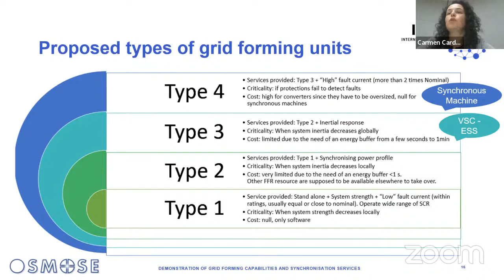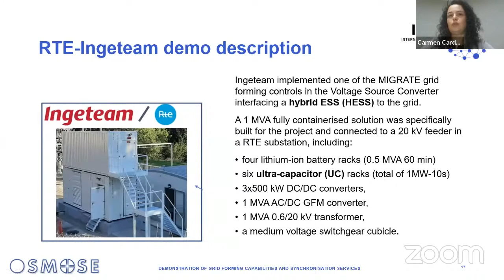So how do we demonstrate that we can achieve this type 3 grid forming capability with off-the-shelf equipment available on the market today? Well, we deployed this demonstrator with Ingeteam. We have these batteries, an ultracapacitor, then 3 DC-DC converters to manage this hybrid system, then this 1 MVA AC-DC grid forming converter. In this container, we also have a transformer and a medium voltage switchgear cubicle to connect to a 20 kilovolt bus bar. And this is what the system looks like. This is the upper storage container, and this is the converter side, the transformer, and the switchgear that are in the lower container to connect to the 20 kilovolt bus bar.